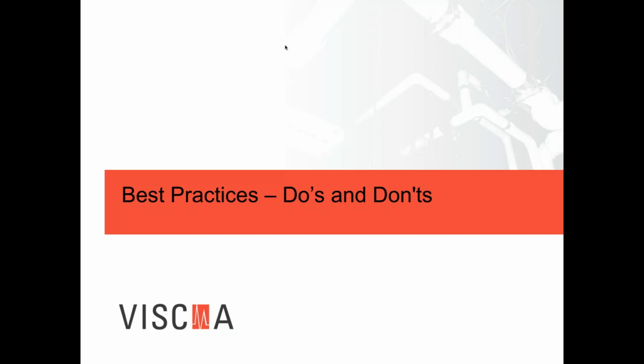Then somebody brought up a question about Chapter 48 in ASHRAE. It's worth repeating rather than answering it independently. The question was whether their assumptions in Chapter 48 are overly conservative. I actually look at conservative as a subjective term, and I made sure I highlighted and stressed that the members of ASHRAE 48 have many years of experience. So maybe analytically, something may show as a little overly conservative, but it comes from practical experience, knowing what to do and what not to do. You may wonder why something is requesting 3.5 inches of deflection when analytically it doesn't show so, but I put my faith in the experience of those engineers, that there's a reason, that they've had issues, they've seen, and they understand. But if you really would like the answer whether the charts in Chapter 48 are overly conservative, I'd send ASHRAE TC 2.6 that question and see the answer that comes back.